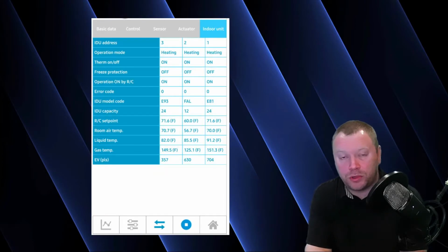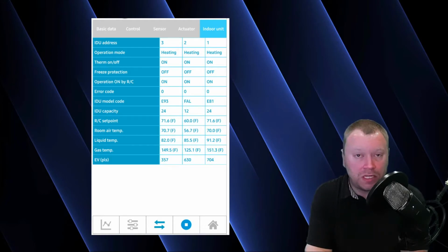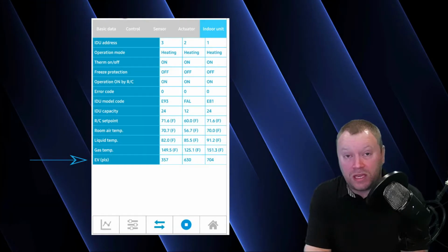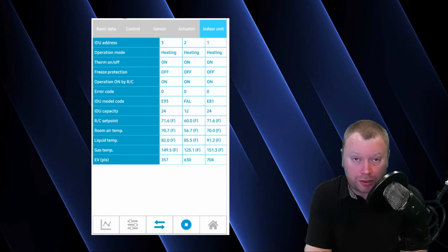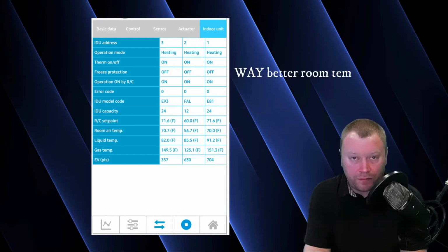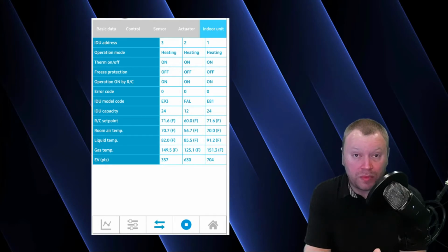Now, we're going to push pause just for a minute because the indoor units on VRV equipment are designed much differently than a mini split. On a mini split, I don't have an expansion valve, but you can clearly see here EV pulses. Every indoor unit on a VRV system has its own electronic expansion valve. This allows for several advantages. One of the advantages that we can talk about today is better refrigerant management, better refrigerant control. Ultimately, this gives you better comfort and higher levels of efficiency when compared to mini split or mini split multi-zone systems.